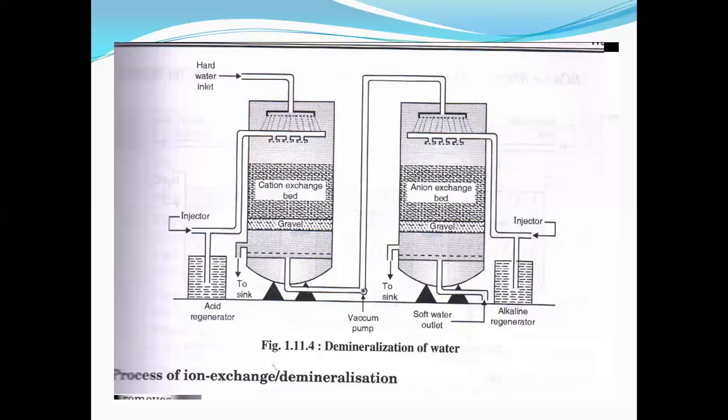So here also, the cation exchange bed and anion exchange bed get exhausted by softening a certain amount of water. Suppose we have softened a million liters of water through it. After that, all the H plus ions in the cation exchange bed are removed and it is completely blocked by calcium and magnesium. And in the anion exchange bed, all the OH minus ions have been removed and only chloride, sulfates, nitrates are stuck in that bed. Now their capacity is lost, both for the cation exchange bed and the anion exchange bed.